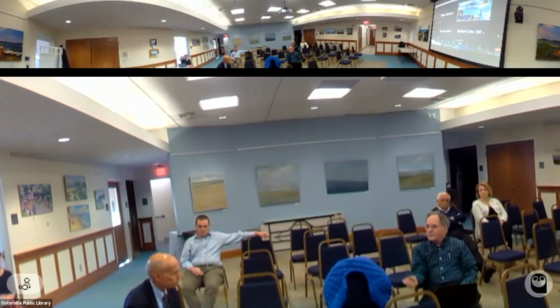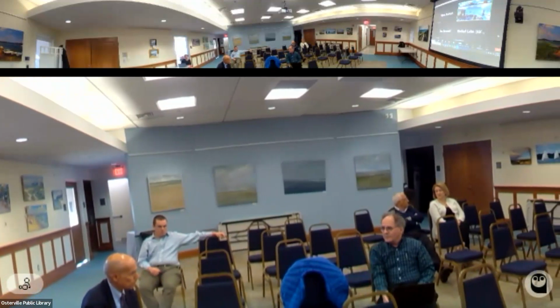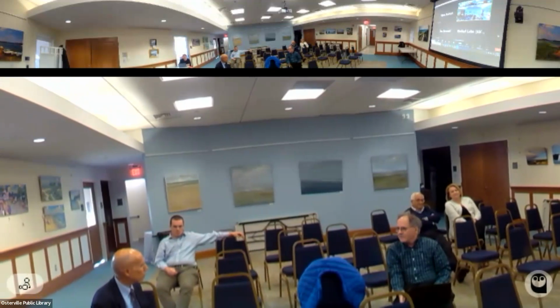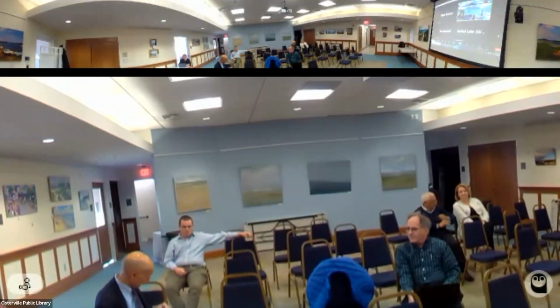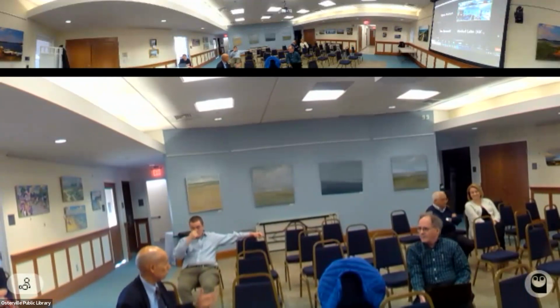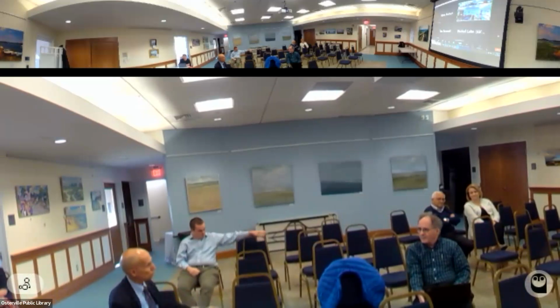Okay. Are the splice vaults for Vineyard Wind 1/2 mile apart? Roughly the same. And so they're roughly 10 splice vaults? Something along that line. It's 7 miles or whatever. If you attended the Park City presentations, the cables get pulled through the splice vaults, as we were talking earlier. Literally pulled. Right. Grab the end of the cable and, using winches, they pull it through.